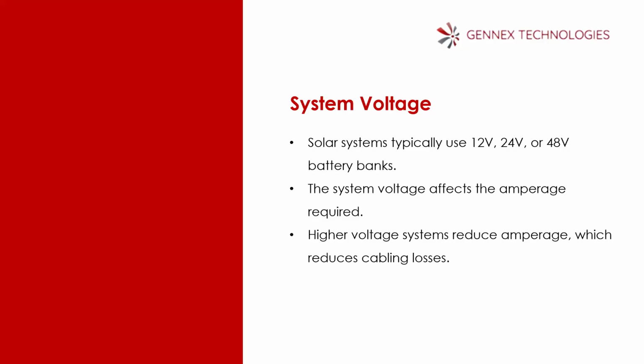A higher voltage system reduces amperage, which reduces cabling losses and even the cost of cable. The cost of cable at the end of the day will be reduced because instead of using maybe 16 mm, since the voltage is higher, you may end up using maybe 10 mm. That's just an example, not saying you should connect 10 mm to a 12 volt system, but that's sizing in terms of cable.